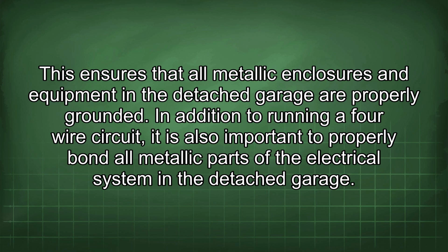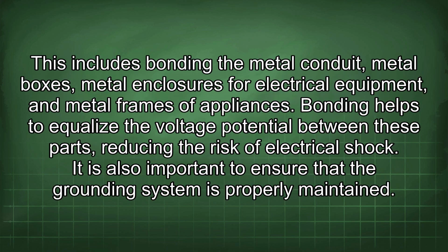In addition to running a 4-wire circuit, it is also important to properly bond all metallic parts of the electrical system in the detached garage. This includes bonding the metal conduit, metal boxes, metal enclosures for electrical equipment, and metal frames of appliances. Bonding helps to equalize the voltage potential between these parts, reducing the risk of electrical shock.